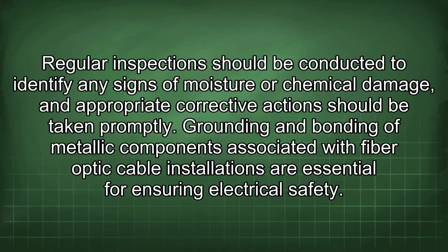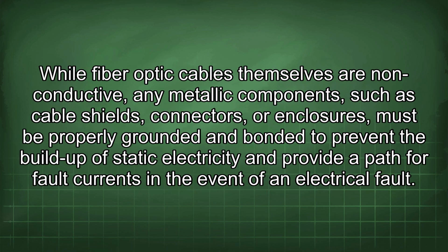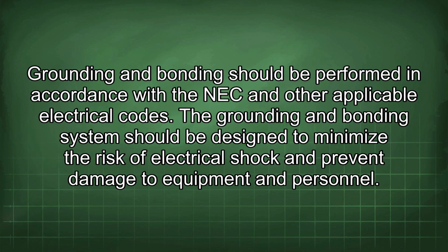Regular inspection should be conducted to identify any signs of moisture or chemical damage, and appropriate corrective action should be taken promptly. Grounding and bonding of metallic components associated with fiber optic cable installations are essential for ensuring electrical safety. While fiber optic cables themselves are non-conductive, any metallic components, such as cable shields, connectors, or enclosures, must be properly grounded and bonded to prevent the buildup of static electricity and provide a path for fault currents in the event of an electrical fault. Grounding and bonding should be performed in accordance with the NEC and other applicable electrical codes. The grounding and bonding system should be designed to minimize the risk of electrical shock and prevent damage to equipment and personnel.